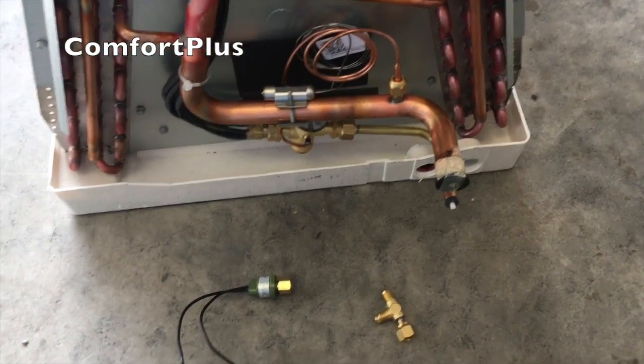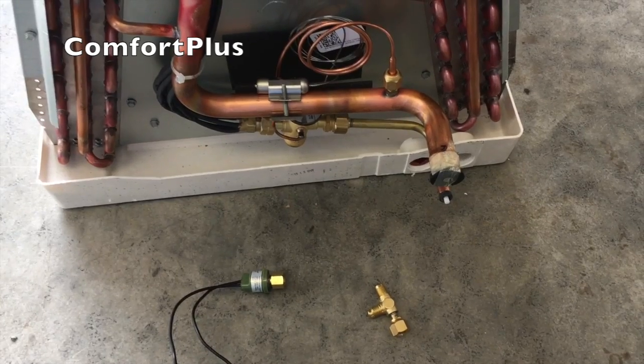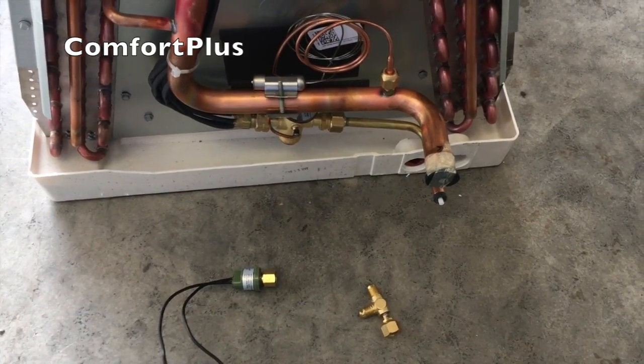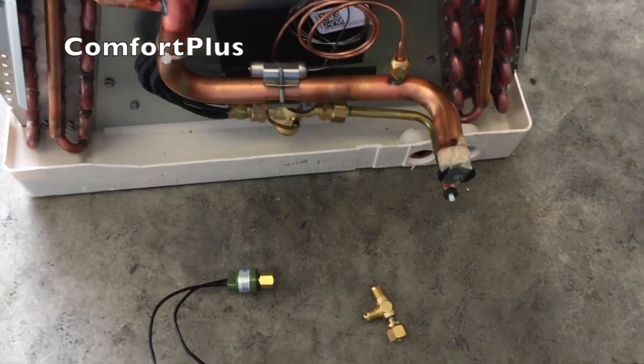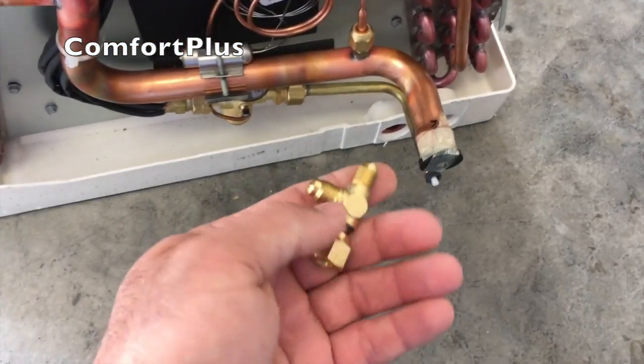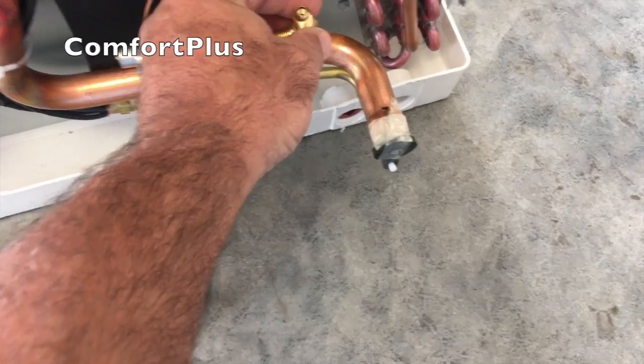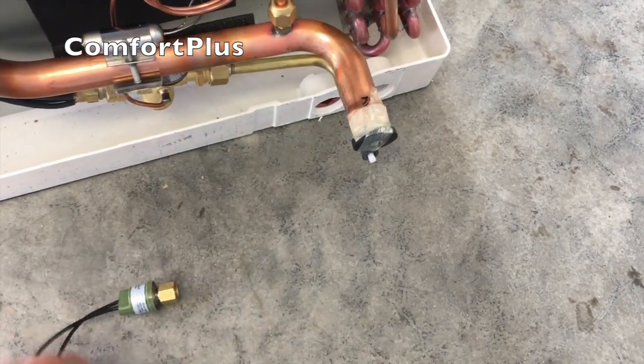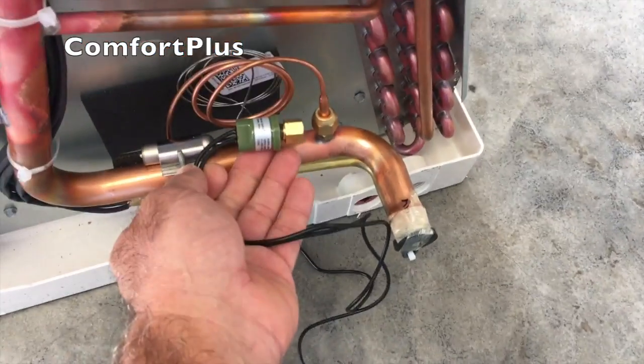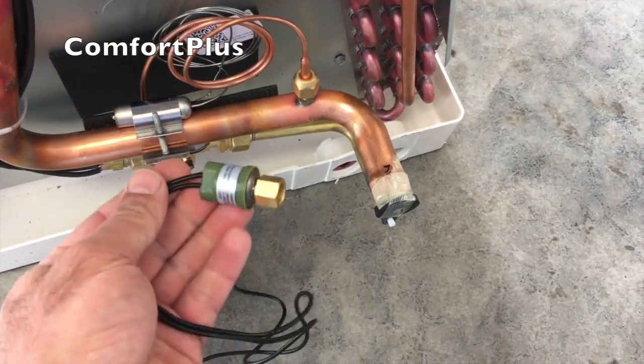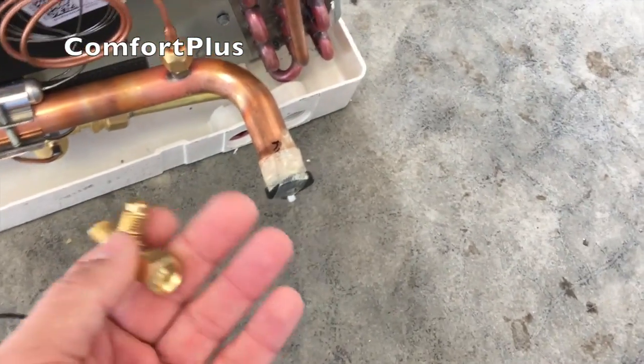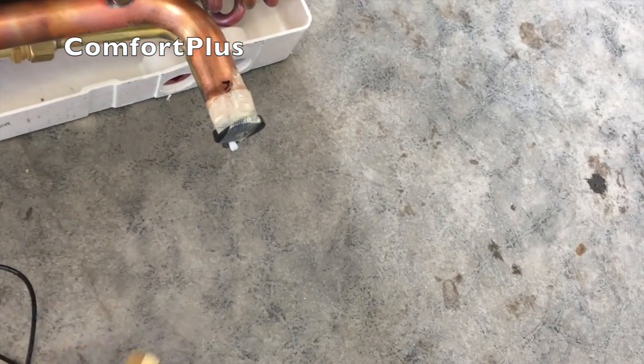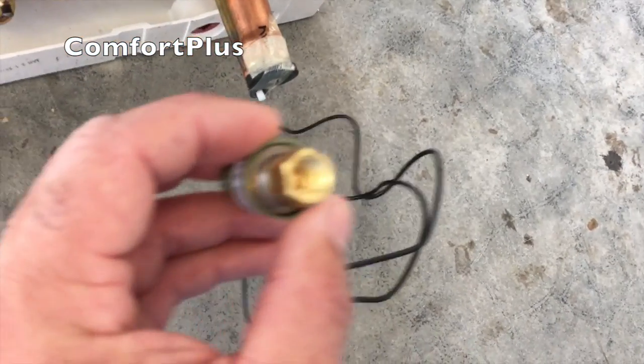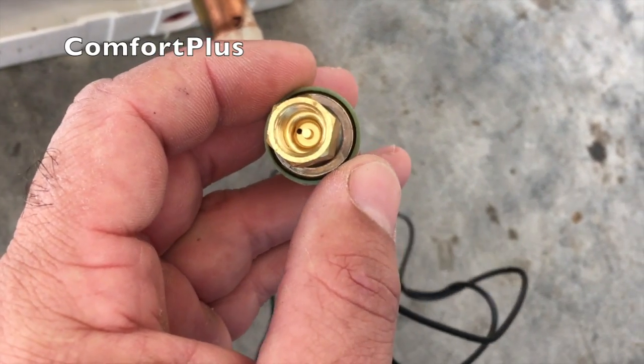Okay, I'm going to put the pressure switch on so the zoning system will know if they're not getting enough air across the coil in heat mode. Just picked up this T. I'll put it on here. The pressure switch will probably end up going right here, and the equalizer line will just connect to the top. There'll be no valve core between the line and the equalizer. However, I'll leave a valve core on the pressure switch just in case I ever need to change it.